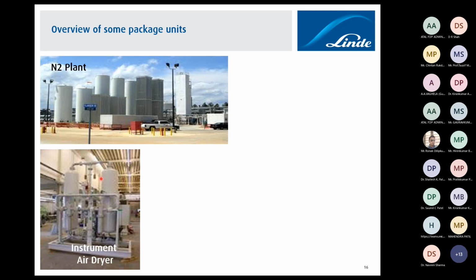Instrument air dryer is a very simple one. It is an adsorption process, with two vessels filled with adsorbent, activated alumina or silica gel, which are very widely used as adsorbents. One unit is in operation and the other is always in regeneration. For regeneration, sometimes compressed air from a high temperature compressor is used, and sometimes an electrical heater is used. Both units operate one by one, so at any given point of time one unit is always in operation. This is how instrument air is used in industries, and typically the end objective is to minimize the dew point.